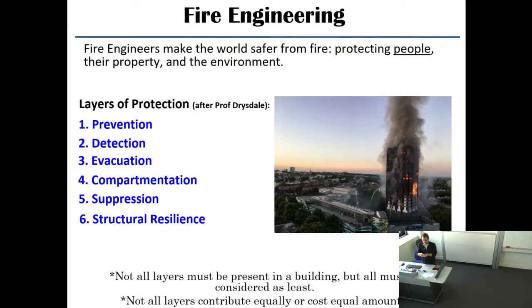And if the glass had activated because it was hot, chances are very high that the fire is not very far. So you are like closing your eyes and thinking, hopefully the fire is there. Okay? And sprinklers are very, very reliable. The technology is inexpensive, the activation itself, but it requires a system of its own. It requires water supply of its own. And the most important thing is, you install this system, it has to be ready every second of the life of the building, and it will only be activated maybe once in the lifetime of the system.